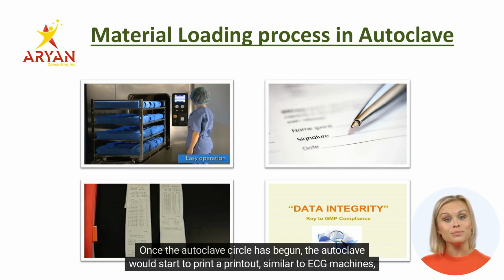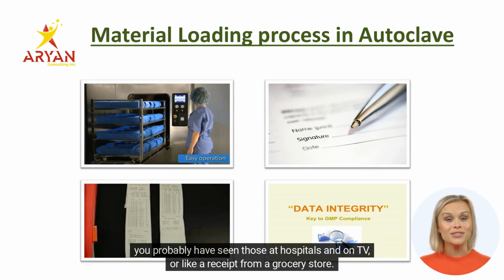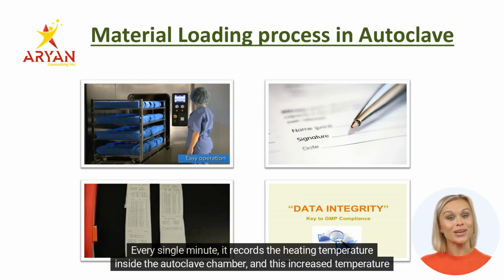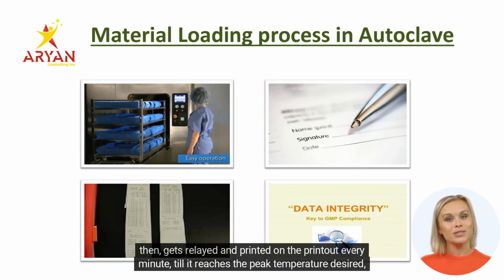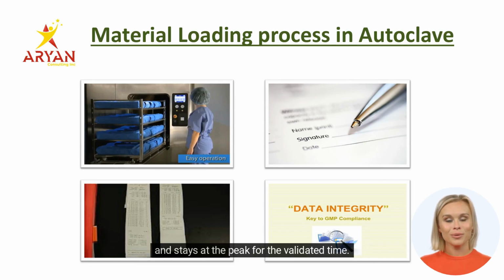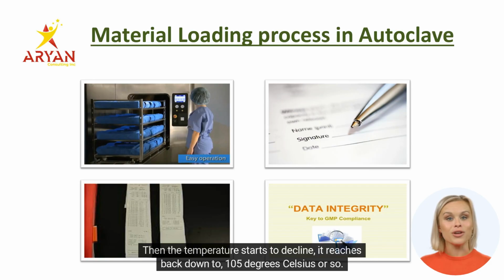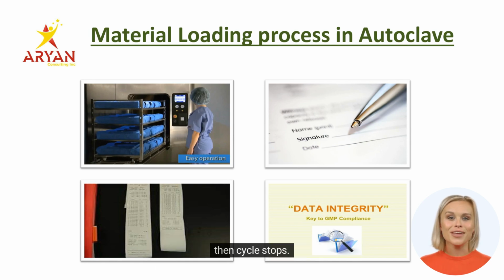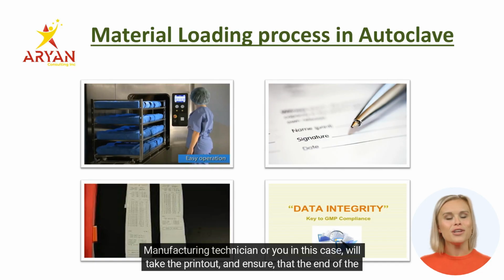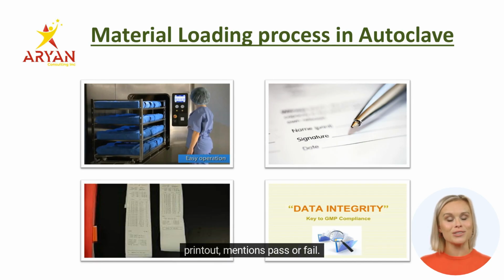Once the autoclave cycle has begun, the autoclave would start to print a printout similar to ECG machines. You have probably seen those at hospitals and on TV, or like a receipt from a grocery store. Every single minute, it records the heating temperature inside the autoclave chamber, and this increased temperature gets relayed and printed on the printout every minute, till it reaches the peak temperature desired and stays at the peak for the validated time. Then the temperature starts to decline, and it reaches back down to 105 degrees Celsius or so. Then the cycle stops. The manufacturing technician, or you in this case, will take the printout and ensure that the end of the printout mentions pass or fail.